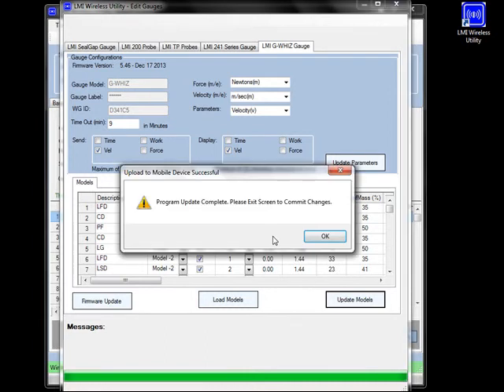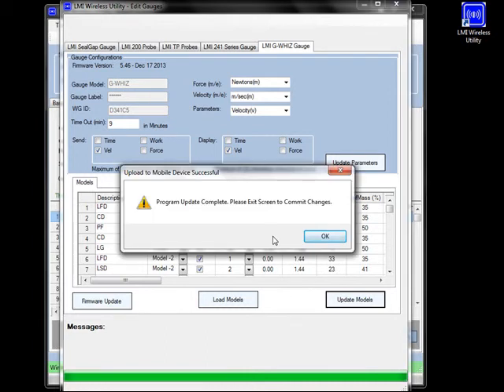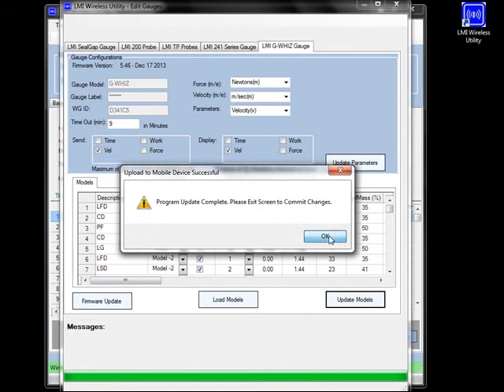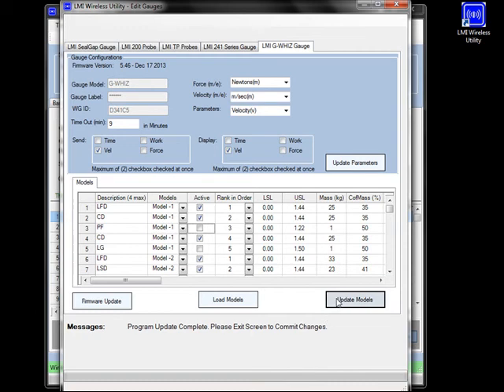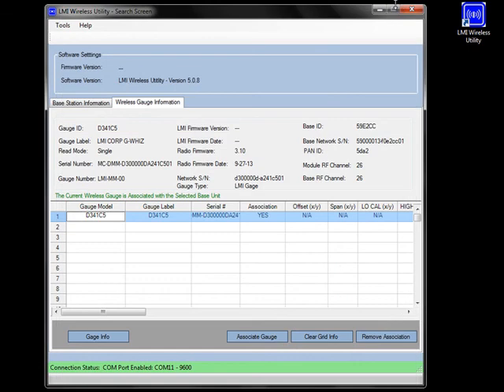So as it finishes, you'll see this little window pop up that says program update complete, please exit screen to commit changes. So in order to commit those changes, what we need to do is we will go up here and click on the red X in the upper right hand corner of the screen. Now if you're looking at your gauge, you're going to notice that what was once the flashing green LED now becomes the flashing red LED. This lets you know that the program was successful in committing to the G-WHIZ. So with that, you can go ahead and begin to take door measurements.